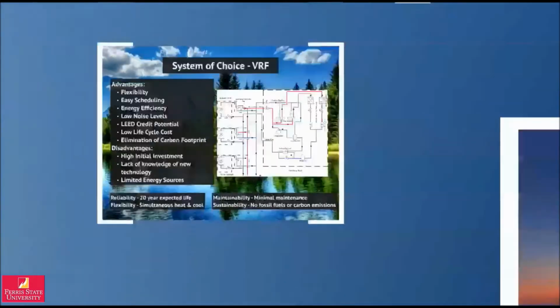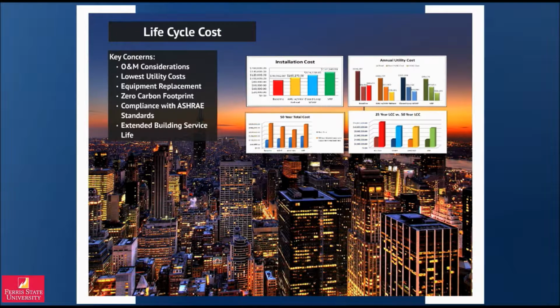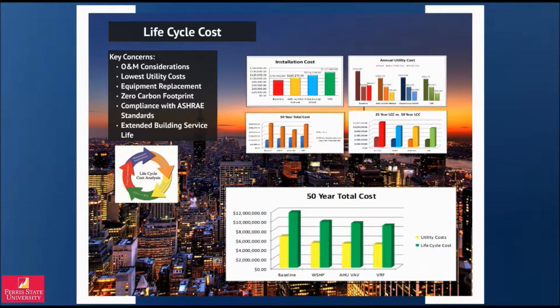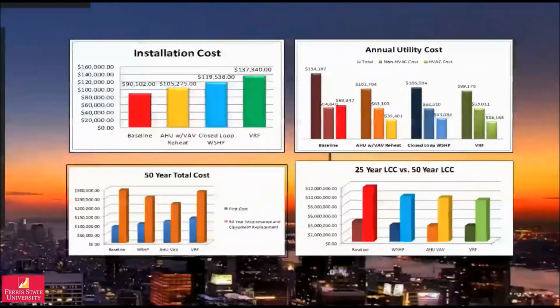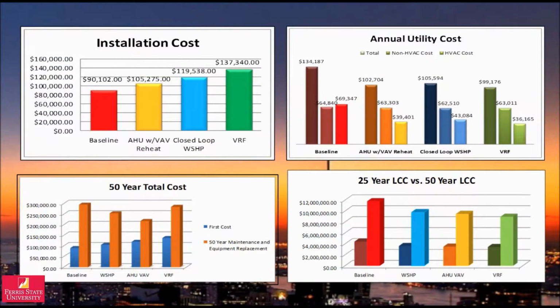In addition to the performance and efficiency requirements of the systems, the overall life cycle costs of each system were evaluated. This research and manufacturing center is considered to be a long-life service building and is expected to have a minimum service life of 50 years, as defined by ASHRAE Standard 189.1. With this in mind, both a 25-year and a 50-year life cycle cost analysis were performed. The DOE2 program was utilized to perform accurate calculations. Future anticipated costs in regards to energy, equipment replacement, and operation were calculated also.